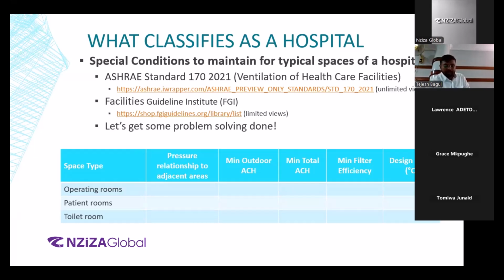Okay. Can anyone give me the first, operating rooms? What was the relationship to adjacent areas? Positive? Yes. Okay. How about the minimum outdoor air changes? 4. Good. Minimum total ACH? 10. How much? 10 or 20? 20. 20? Okay, all right. Minimum filter efficiency? MERV 16. Okay. How about the design temperature? Okay. Good? Yeah. All right. I'll explain everything to you in a moment. Let's talk about the other two areas first.